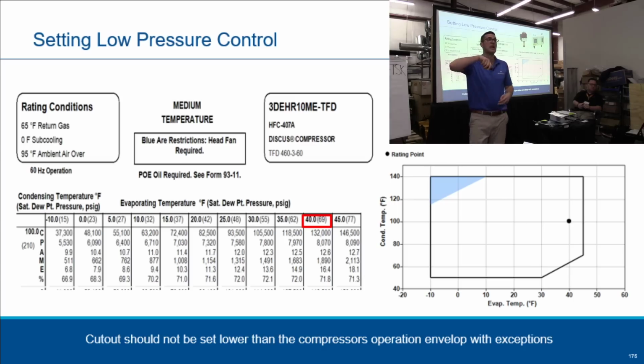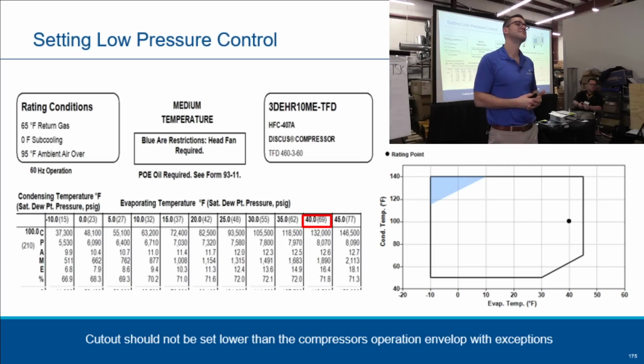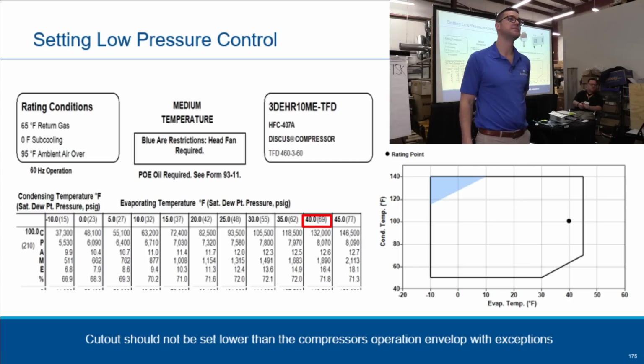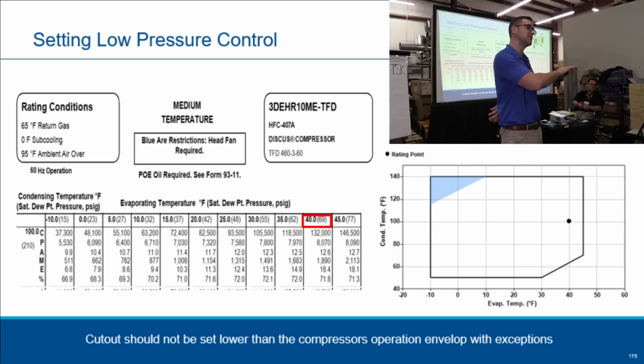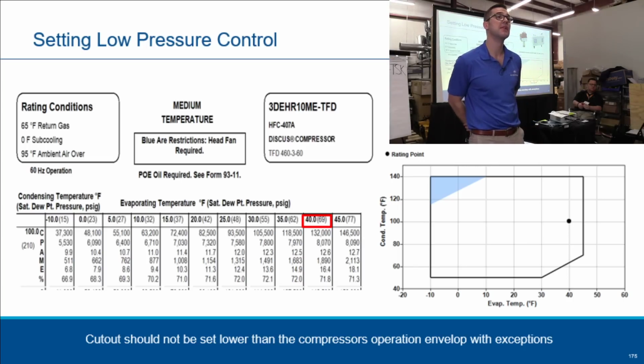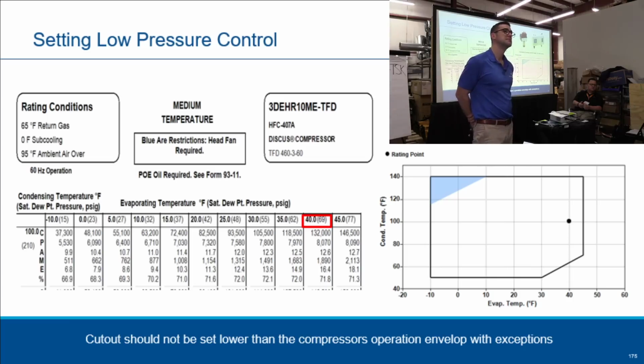Yes, go ahead. Question. I don't do much commercial refrigeration, but if you have a rack that has different temperatures, do you have racks that have different temperatures? Yeah, you'll have a medium temp rack and then a low temp rack. So where do you put the pressure control? Depending. Oh, each compressor. Okay. Yeah, each compressor would have one.